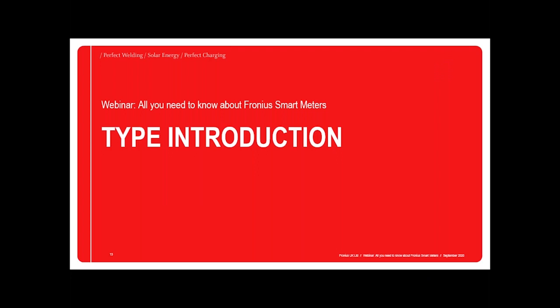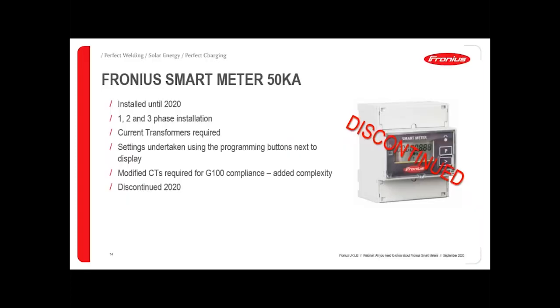So there are a couple of the key functions available from using the smart meter. A number of you may be familiar with the Fronius Smart Meter 50Ka. This unit was installed on pretty much every installation up until 2020. It was available for single, split phase and three-phase installations, and it required current transformers. The programming of this was undertaken using the buttons on the front of the screen — a P button and an arrow button. In order to use this for export limitation, we needed to provide modified CTs, which were quite difficult to install with a lot of additional programming. So this unit has now been discontinued.